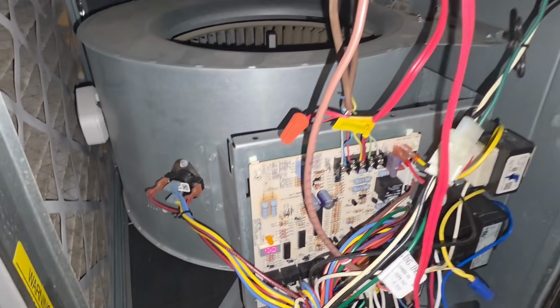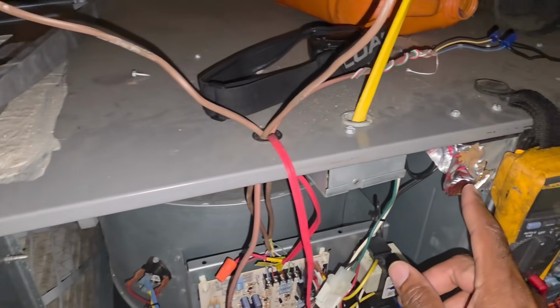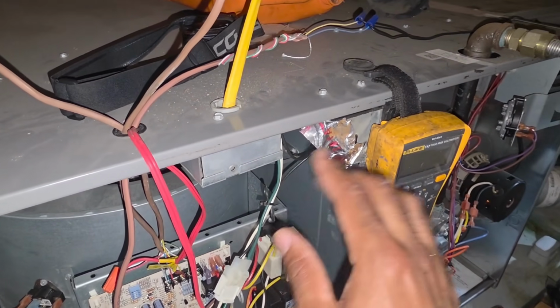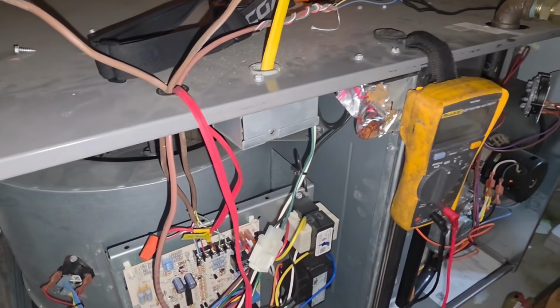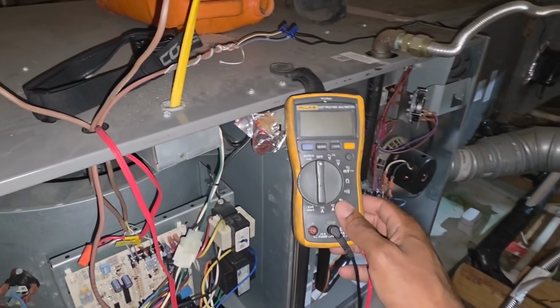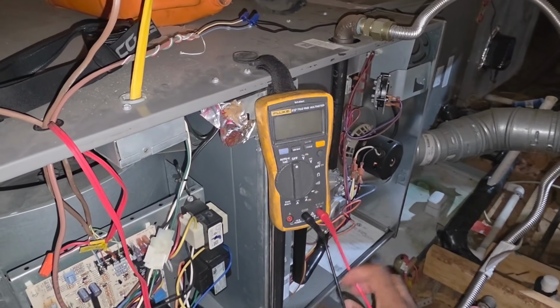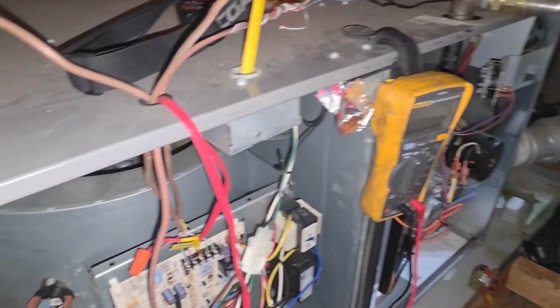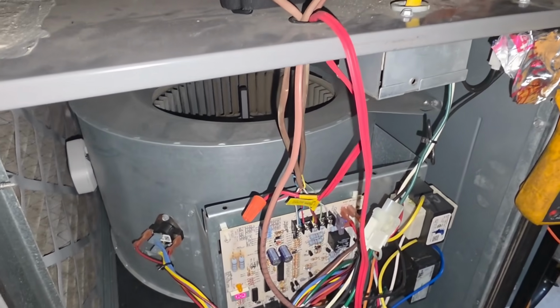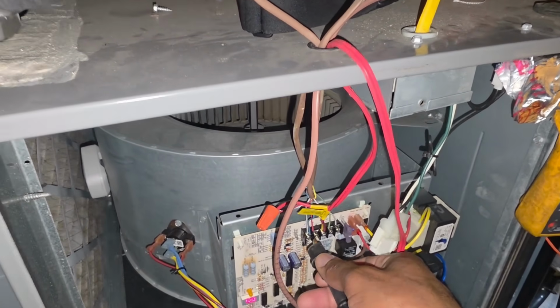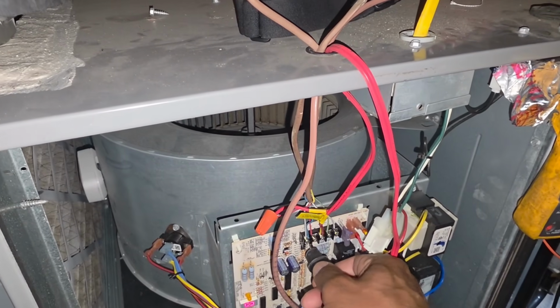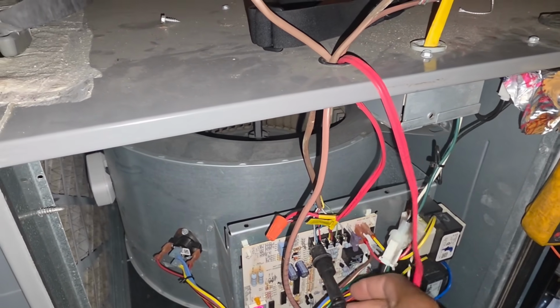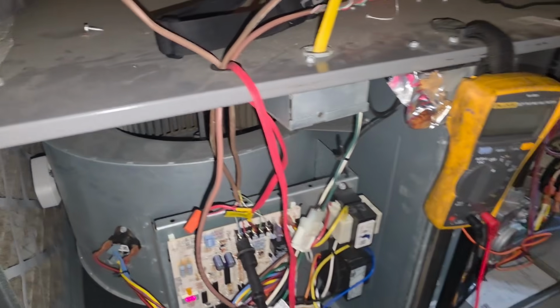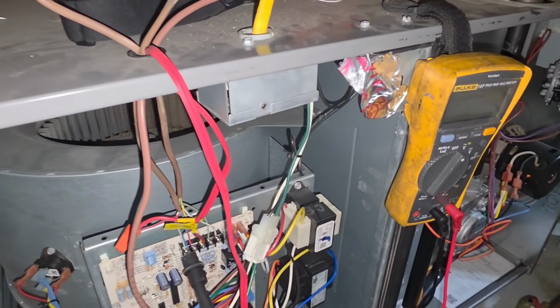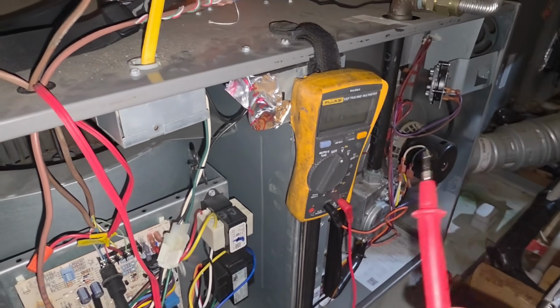All right, so as you can see now, the system is on, it's powered up. I got the pressure door switch bypassed, so I do have voltage to the unit. First, we want to get our meter somewhere where we'll be able to read it. And like I say, the common point we're going to use is where my pivot foot is going to be, on this common right here. So we got us a good common. We'll put our meter on voltage. And this is the pivot method.